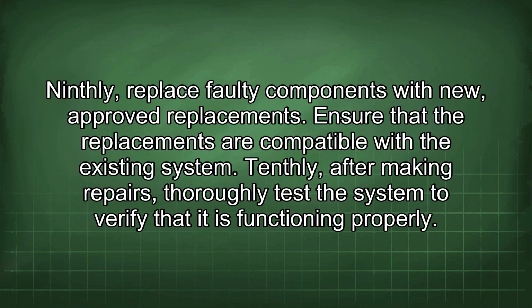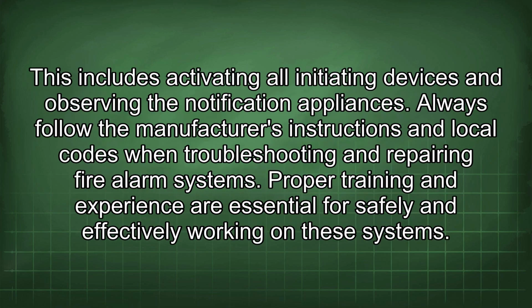Ninthly, replace faulty components with new, approved replacements. Ensure that the replacements are compatible with the existing system. Tenthly, after making repairs, thoroughly test the system to verify that it is functioning properly. This includes activating all initiating devices and observing the notification appliances. Always follow the manufacturer's instructions and local codes when troubleshooting and repairing fire alarm systems. Proper training and experience are essential for safely and effectively working on these systems.